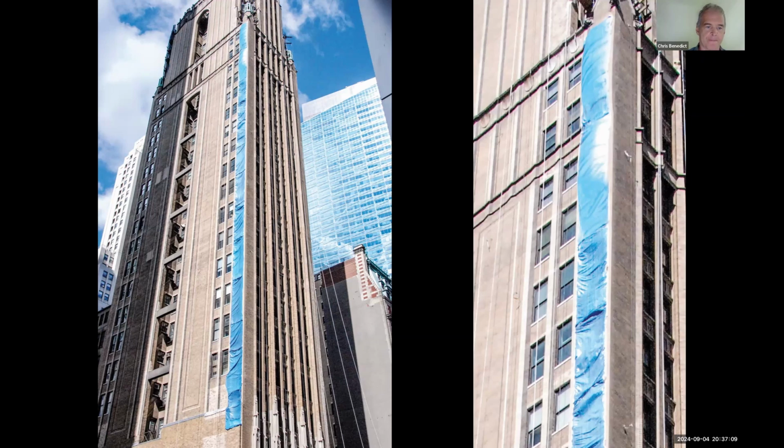I think this makes a lot of sense. The lower part is under negative pressure, the top part is under positive pressure, and there's a neutral pressure plane right in the middle between the two. Well, in this case, the neutral pressure plane is up near the top. It's about 4 stories. It's halfway up the right photo.